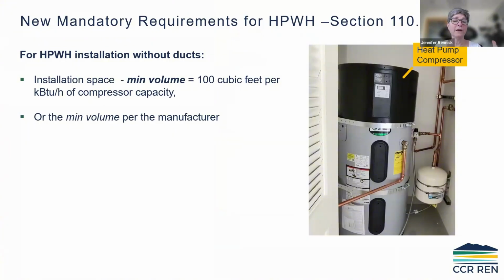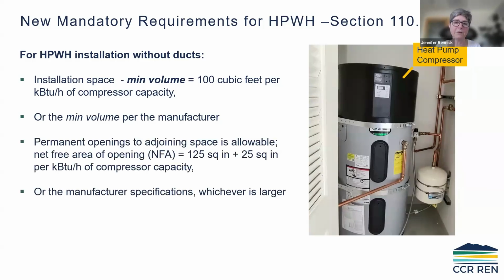The main takeaway though is you've got to follow the minimum volume per the manufacturer, or at least you need to take the compressor capacity and multiply it times 100 cubic feet, and you get a minimum volume. So that's like that 450 because the compressor was maybe a 4.5 kBTU. Permanent openings adjoining the space are allowable.